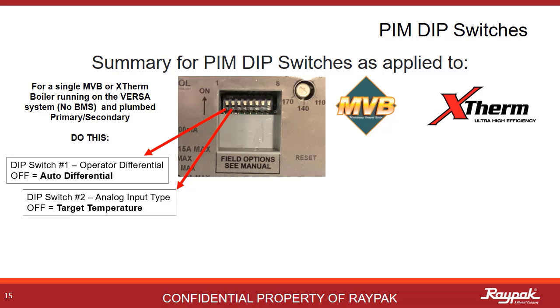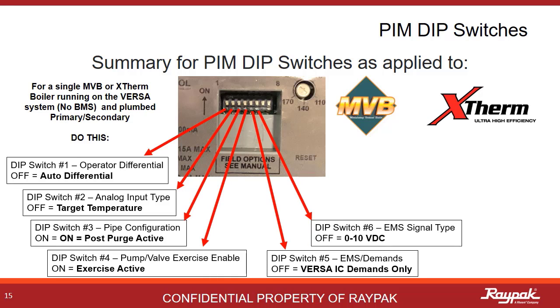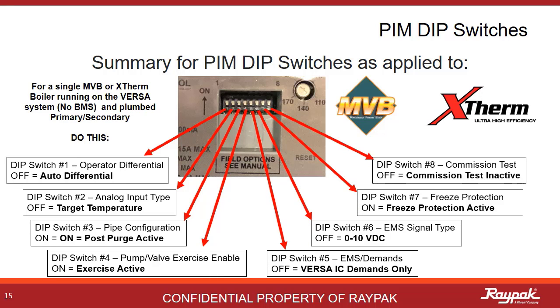Here is the summary for PIM dip switches on the MVB and Xtherm boilers. For a single boiler operating on the Versa system — not on a building management system — and plumbed primary or secondary, turn on dip switches three, four, and seven, and leave the others off. This will enable the post purge feature, allow for pump exercise, and enable freeze protection. Turn on three, four, and seven.